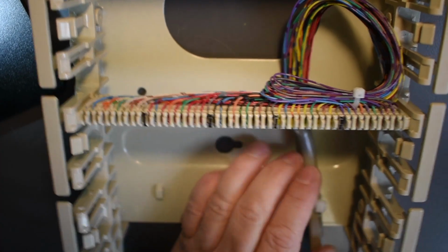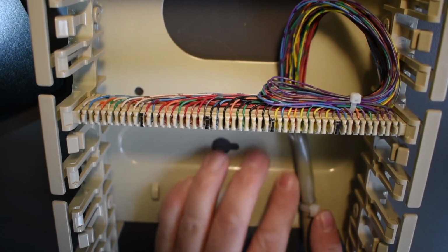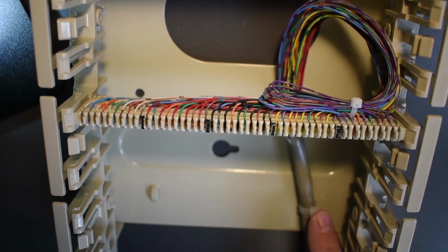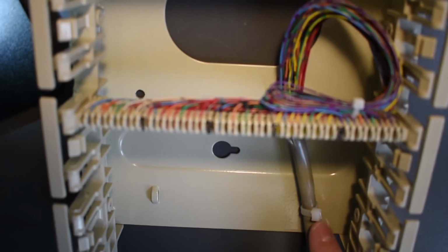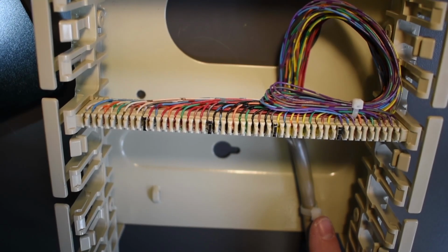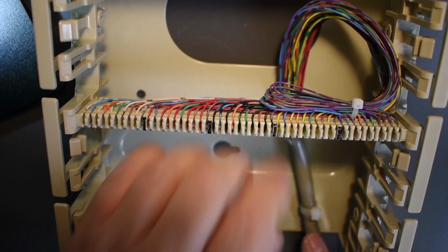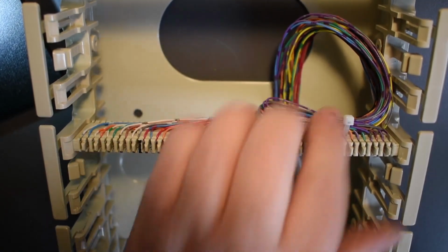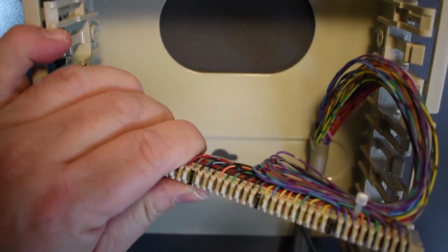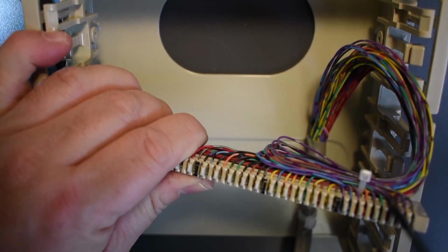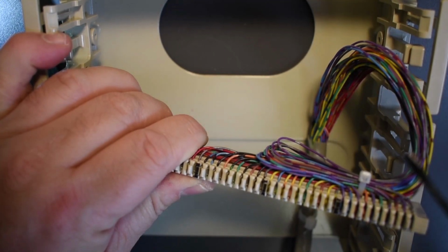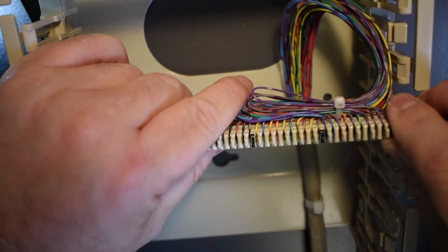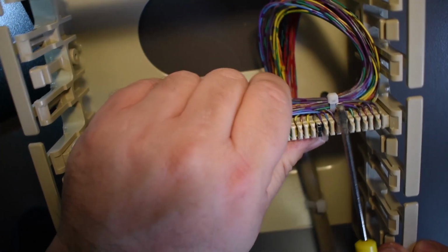I want to see a nice clean mount here with the cable tie or zip tie trimmed right here. That needs to be trimmed. I need to see a nice beautiful slack here that goes right from where the wire jacketing ends right here, all the way nicely and beautifully to here, and nice binding right here.